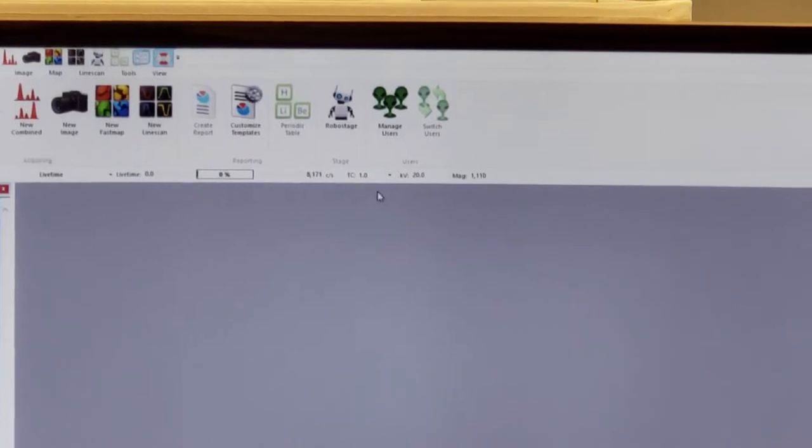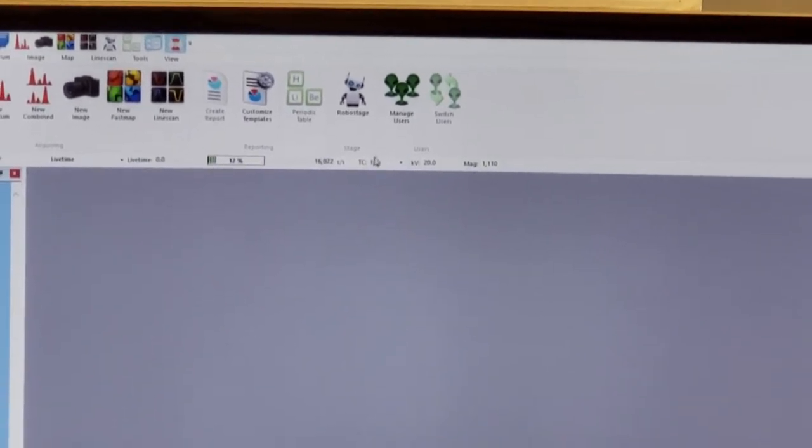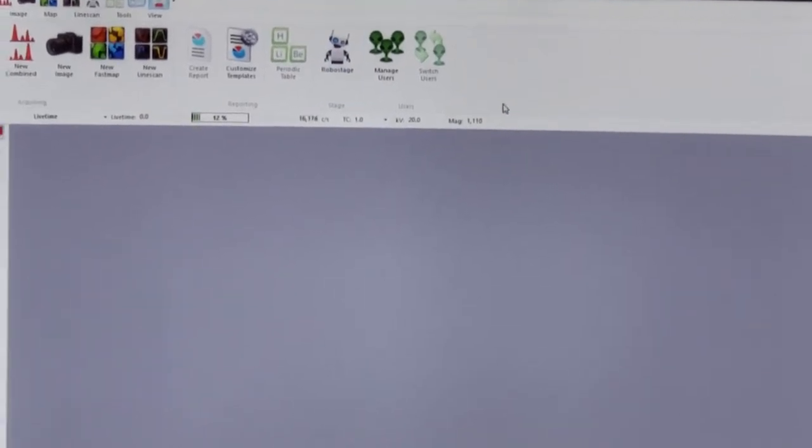So before, I was looking at it like, it's aluminum. Yeah, it's definitely aluminum, no question about it. Now it's like, that's aluminum, right? And if I go to time constant 1 microsecond, it's like, aluminum, right? But again, I'm able to change my time constant, my process information time, strictly for the mapping feature of this software, just to let you know. That's what it's really for.